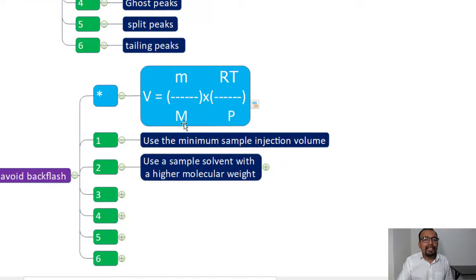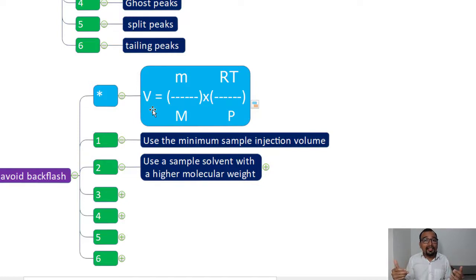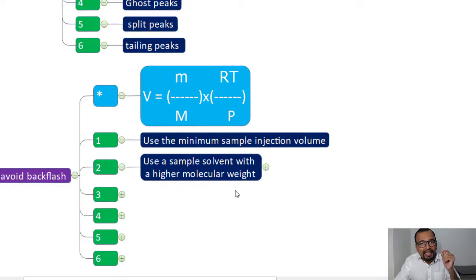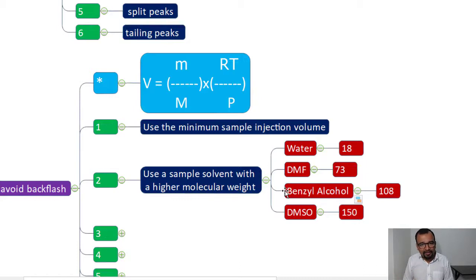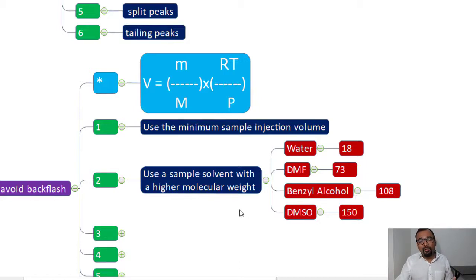The second mitigation point is linked to molecular weight M. Smaller molecular weight produces a bigger volume of vapor; greater molecular weight produces a smaller vaporized volume. So use a sample solvent with a higher molecular weight. Look at common solvents: water has MW 18, DMF has 73, benzyl alcohol has 108, and DMSO has 150. Solvents with higher molecular weight will generate lesser vapor volume.